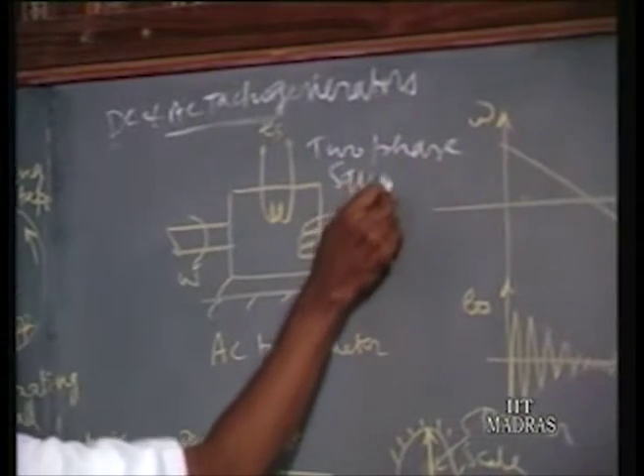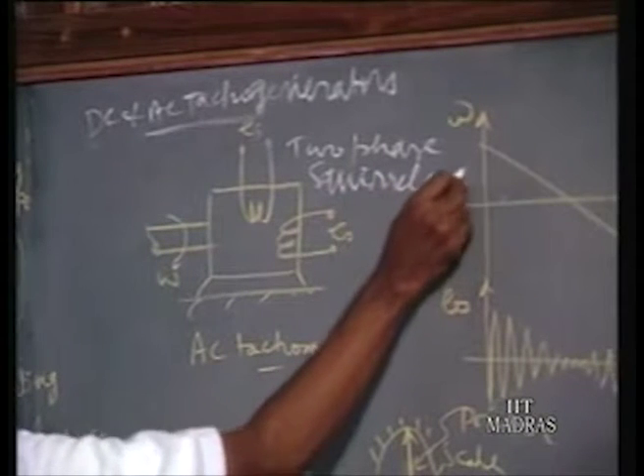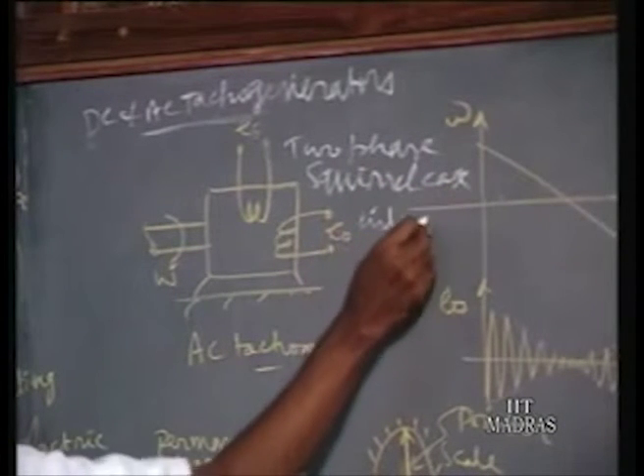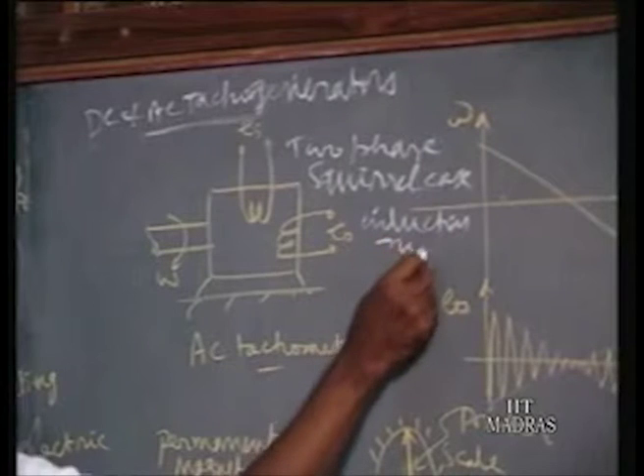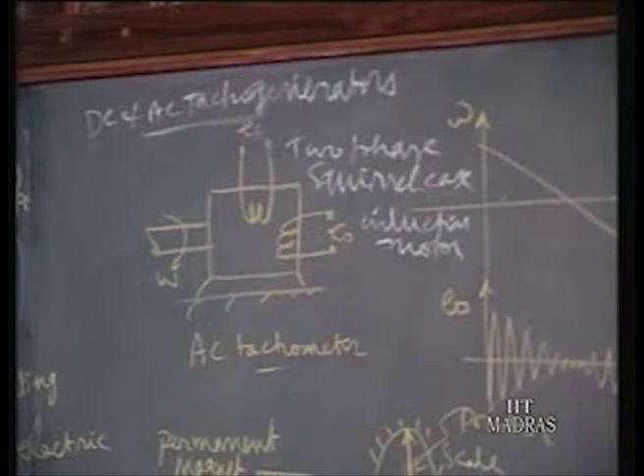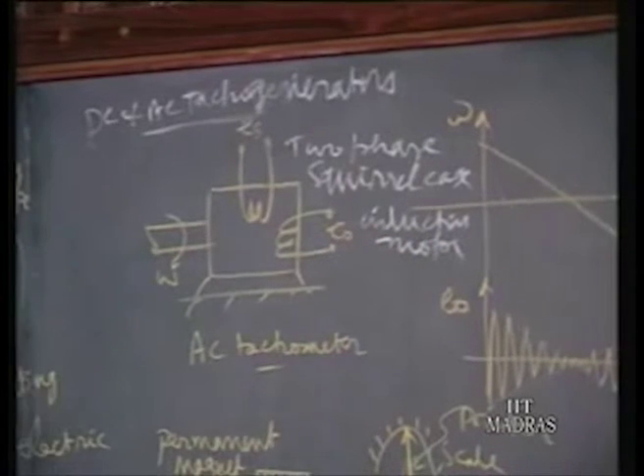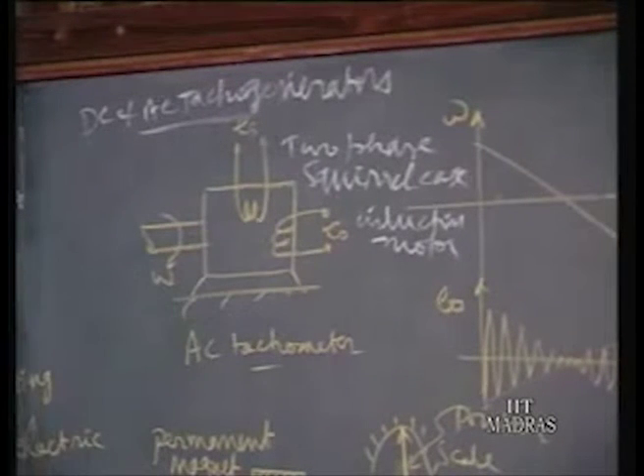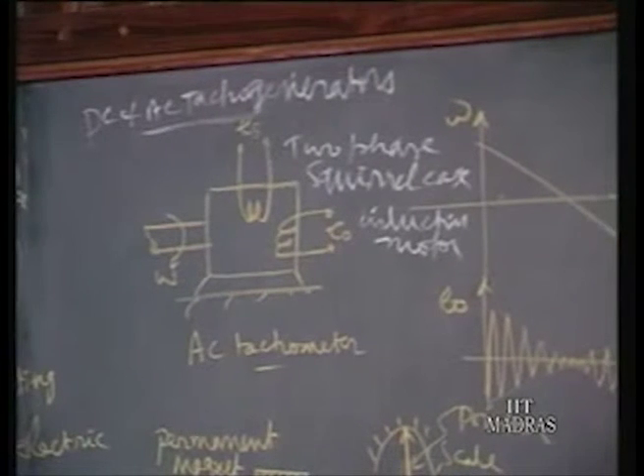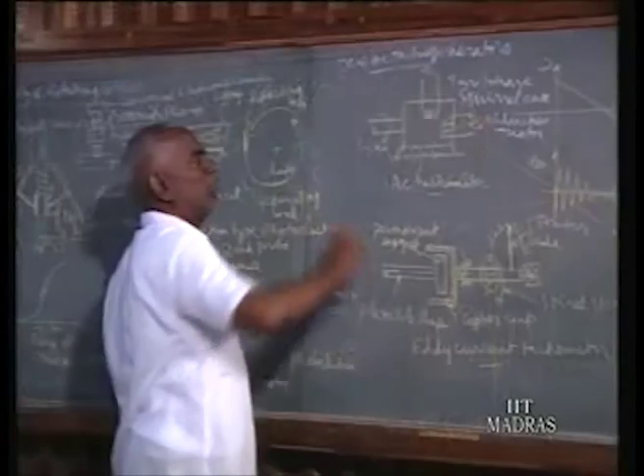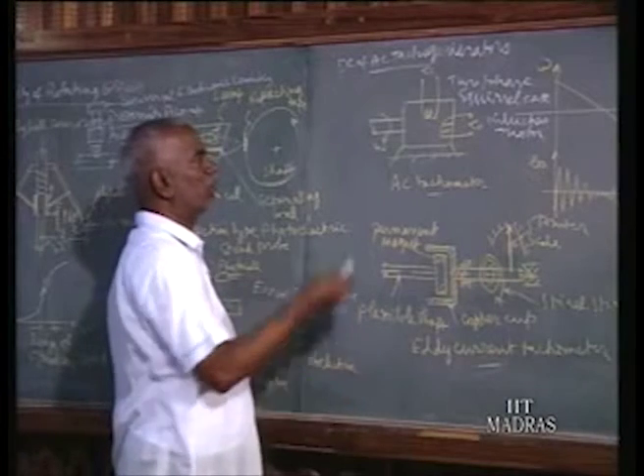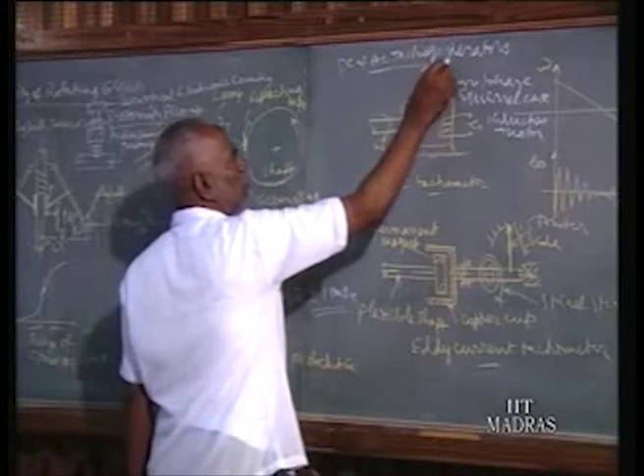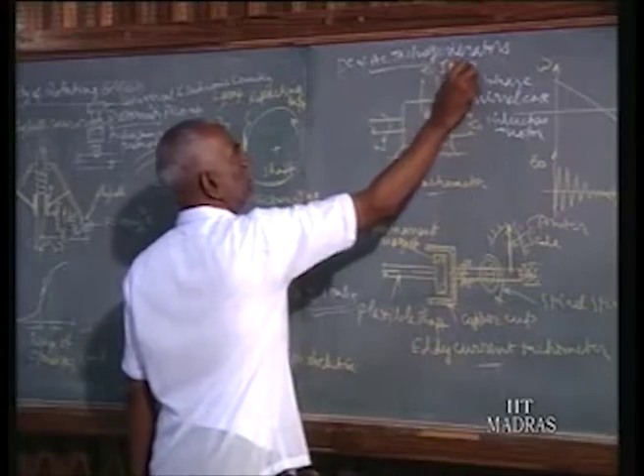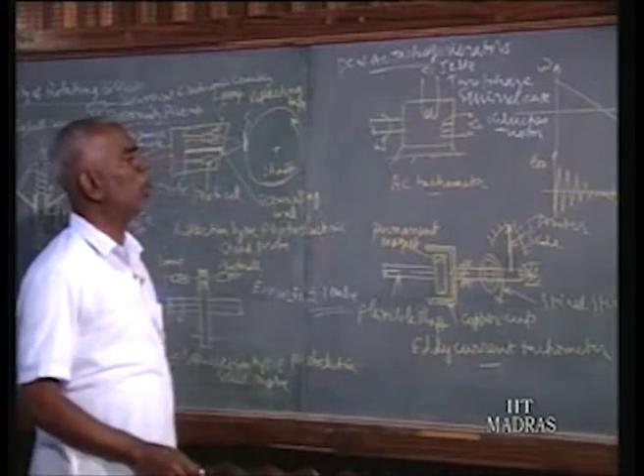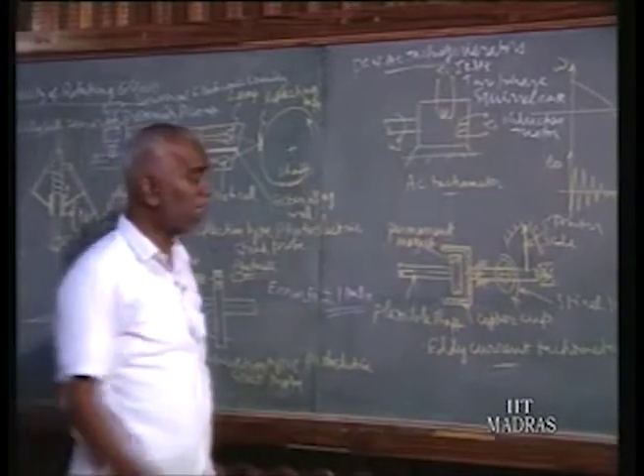squirrel cage induction motor that can be used for measuring speed. What is done is, there are 2 coils at electrically 90 degrees, and you separate them out, and in one of the coils you give the supply voltage, say at a particular frequency, 5 kilohertz for example, and in the other winding you will get the output proportional to speed as per this diagram.